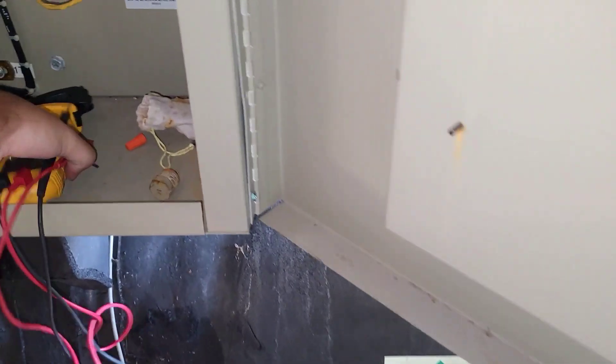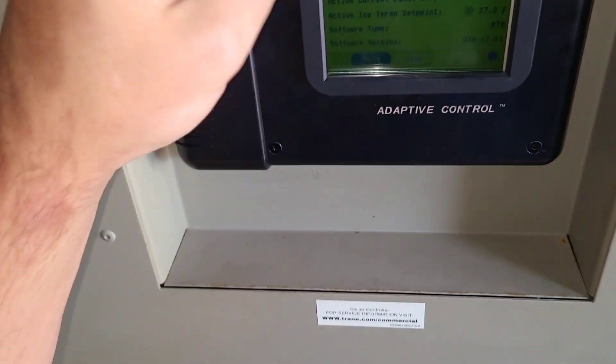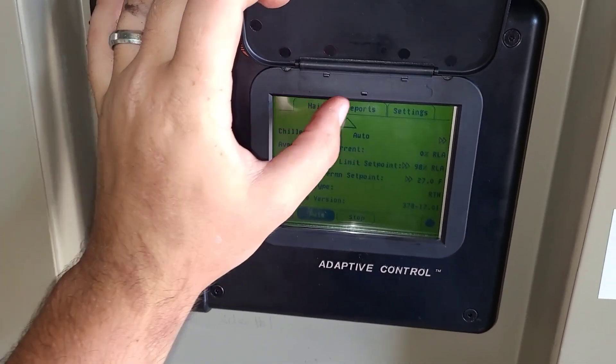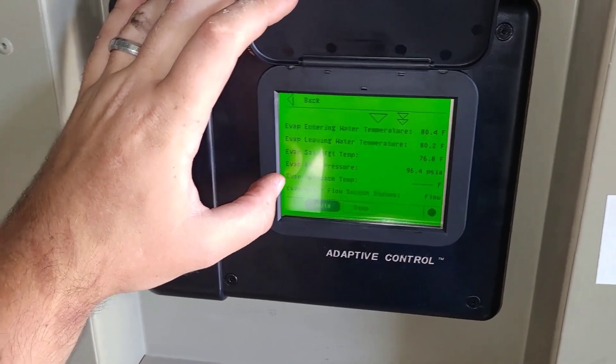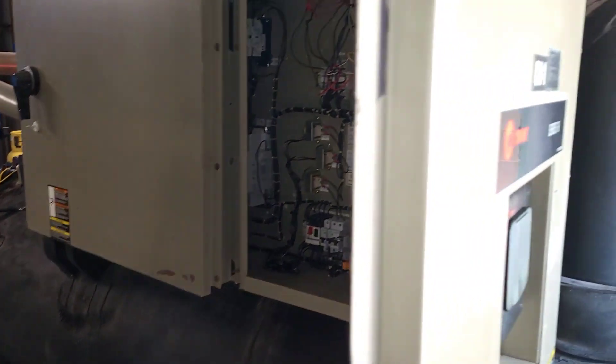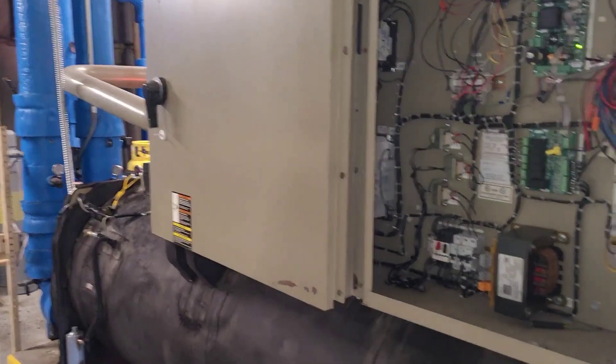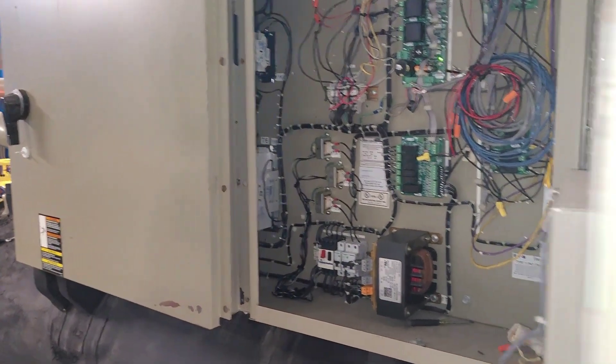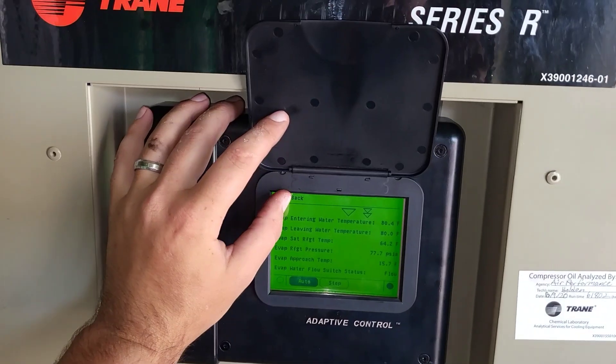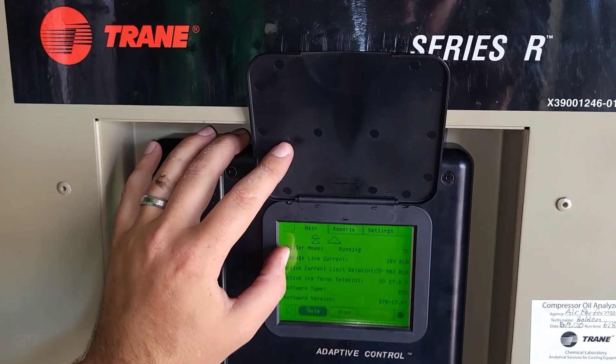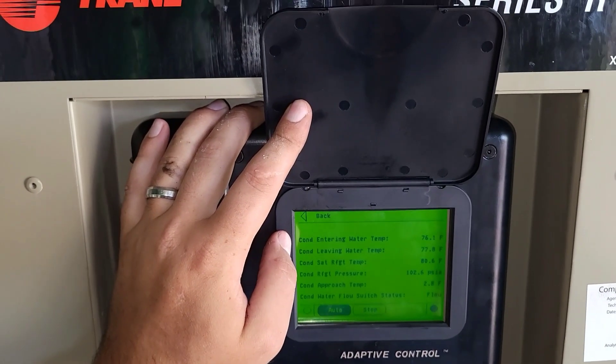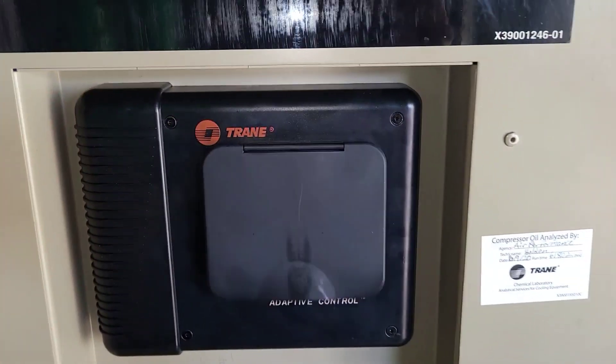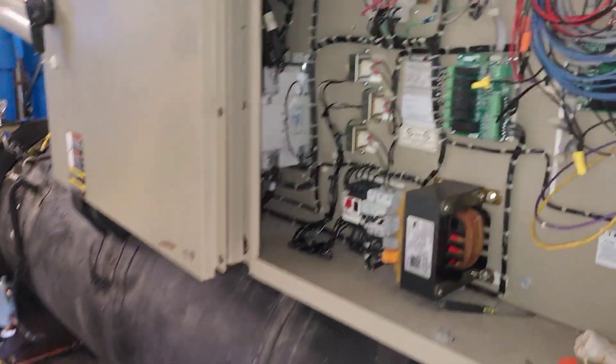All right, now that we got that on, come back here to reports—evaporator flow—and we are up and going. Nice. Just that quick, that's all it needed. And if you're wondering, yes, this machine is that loud. Water looks fine. It'll start staging up and doing its thing. So we'll button everything up.